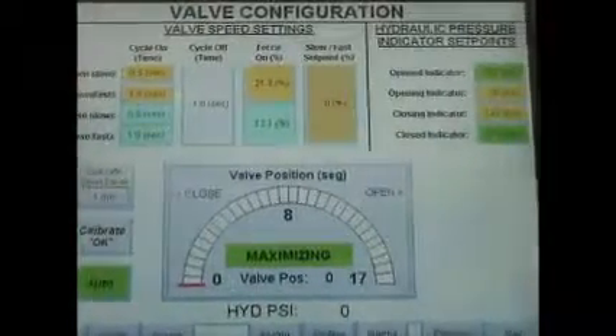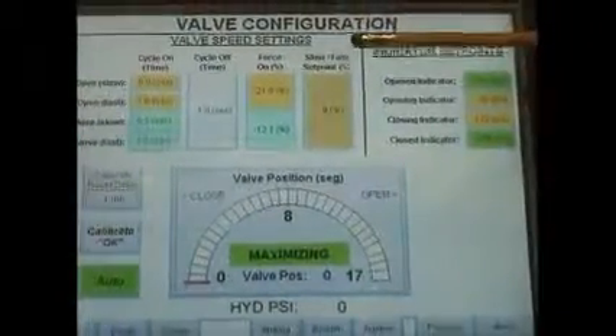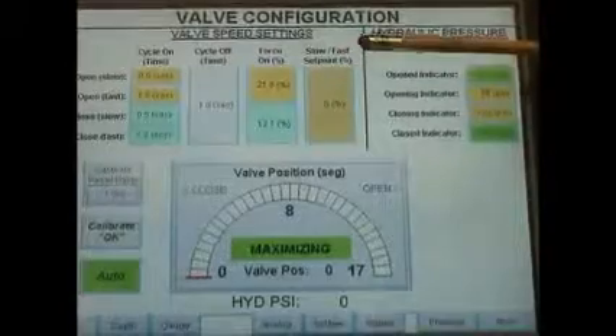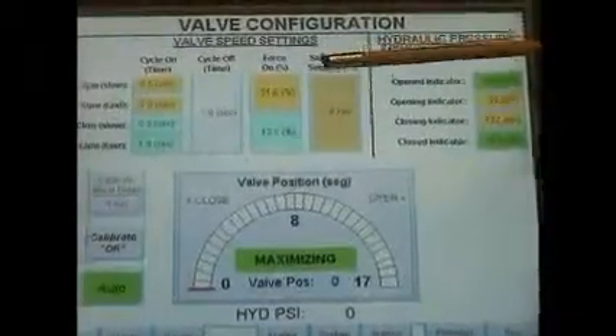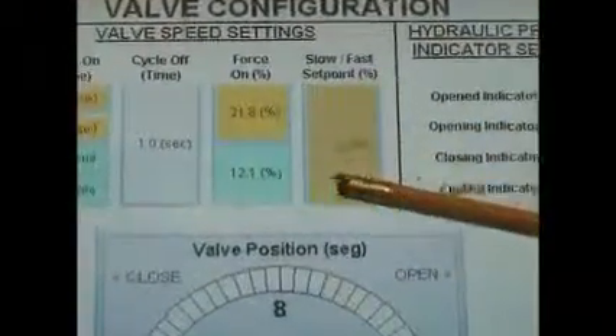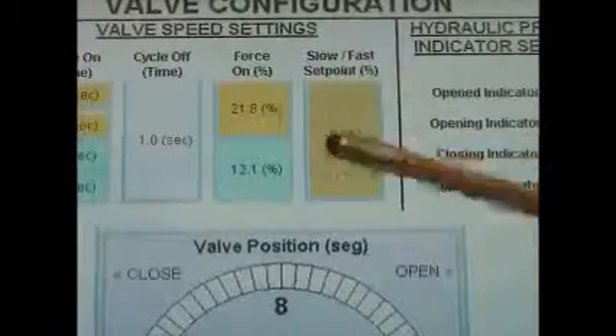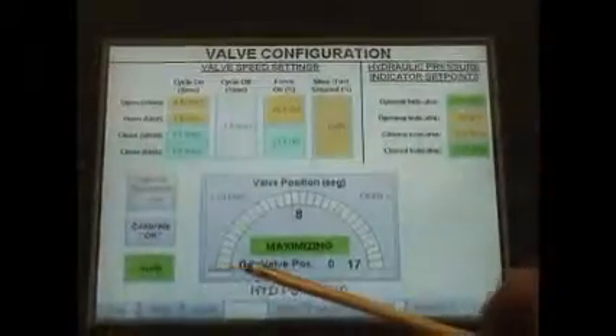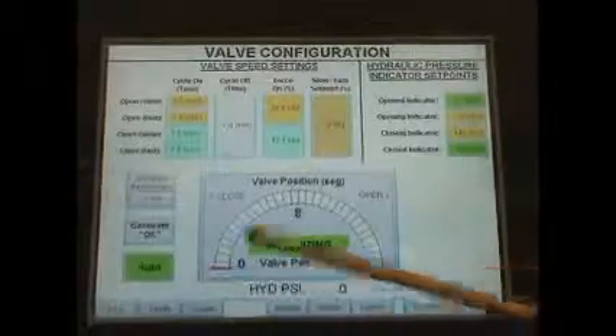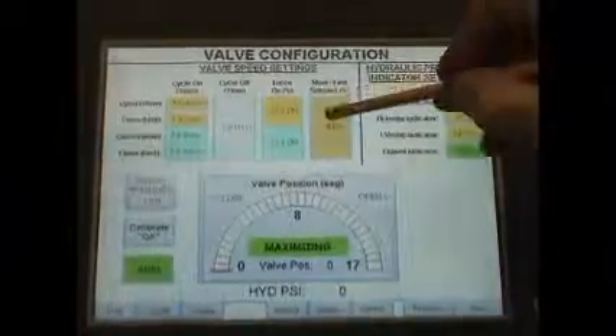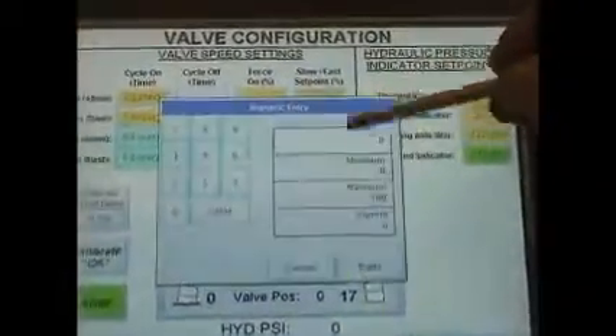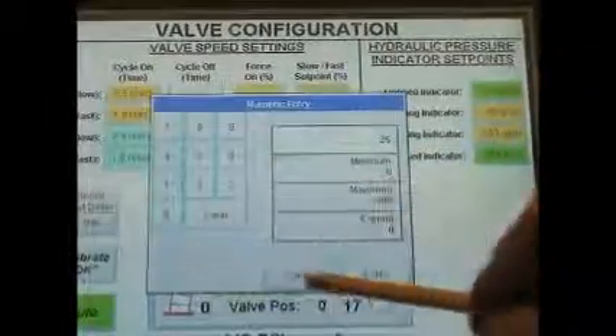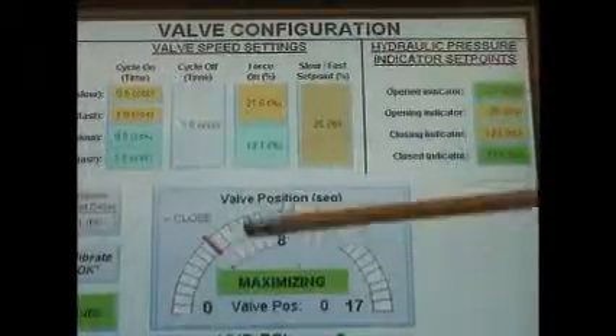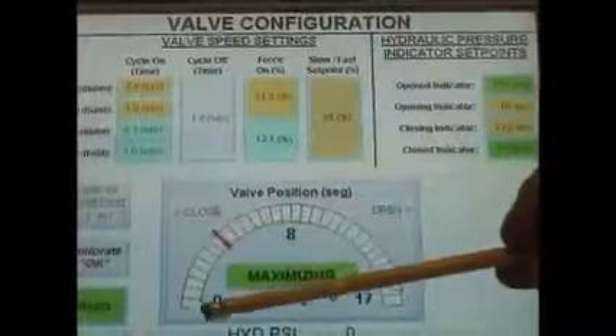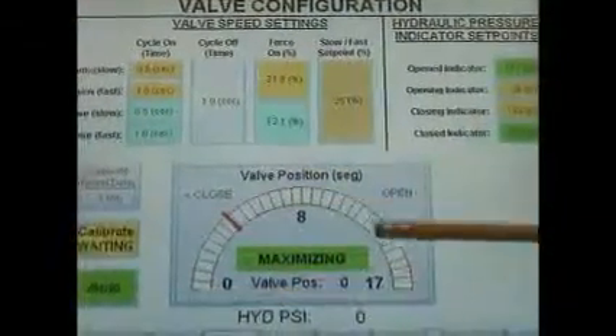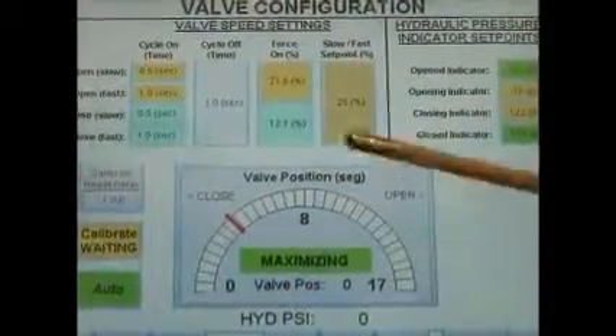The other option we have is what we call our 2-speed option, or our second option, our slow fast set point. Currently our fast set point is set at 0. As you can see, this red line down here is down at 0. If we, for example, set our fast set point at 25%, our red line climbs up to about 25% of the way of our valve position.